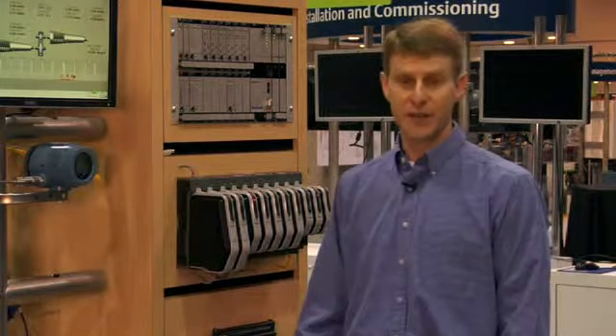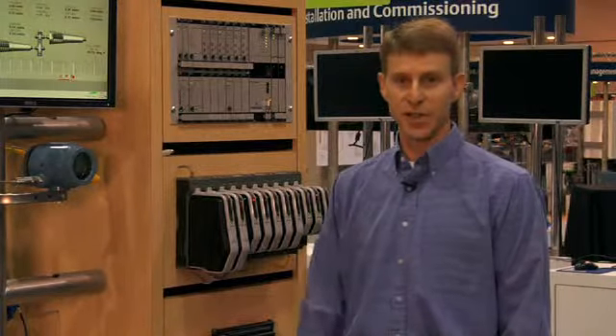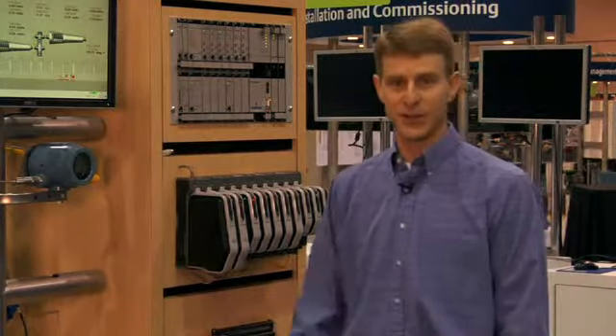All the function blocks are tied together, it includes metric, English units, full scale ranges, all the information is completely configured. In fact, the alarm limits are even automatically set up so that they can be transferred from the protection system automatically. So you can enter the information once and the information is automatically transferred to the Delta V.